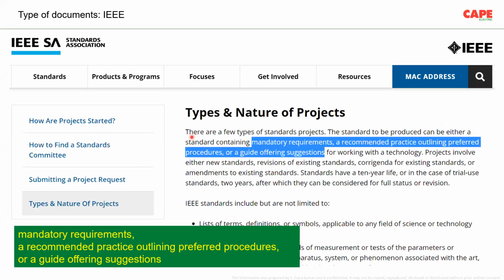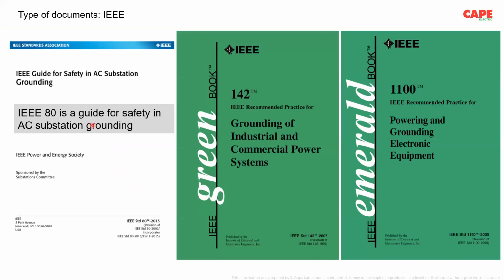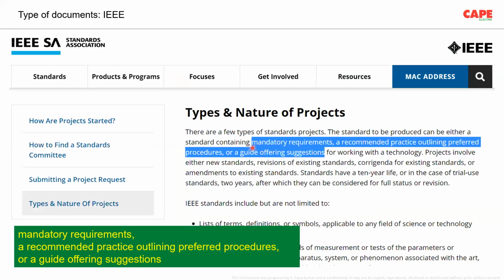Similarly, in IEEE, the standards are classified: a standard to be produced can be either a standard containing mandatory requirements, a recommended practice outlining preferred procedure, or a guide offering suggestions. So there are 3 types of documents. Now I am showing you 3 IEEE standards. IEEE 80, which is a guide for safety in AC substation grounding. So it is guiding to make something. It is not a mandatory requirement. It is not a recommended practice. IEEE 142 and IEEE 1100 are recommended practice. I go back, you see, IEEE: mandatory requirement, recommended practices, and a guide.